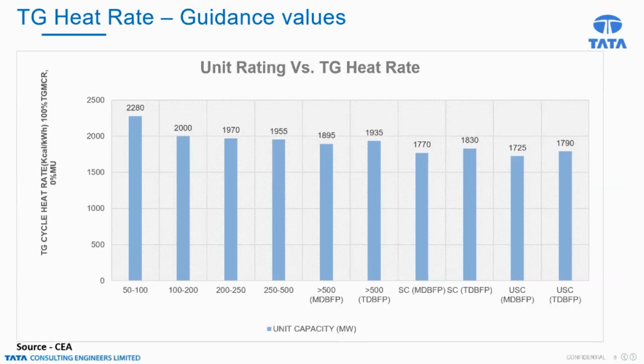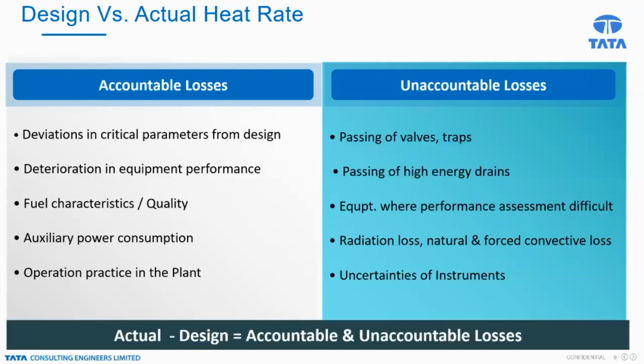In the case of 500 megawatt and above, we have two options: a motor-driven boiler feed water pump or a turbine-driven feed water pump. Accordingly, the heat rate values are defined for reference. When the manufacturers or designers supply the equipment, they guarantee a certain heat rate for the turbine cycle, and in the case of the boiler, the boiler efficiency is guaranteed by the supplier. So we arrive at the unit heat rate. That is the design case.